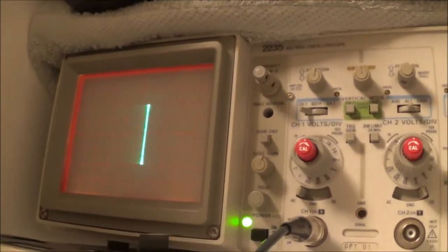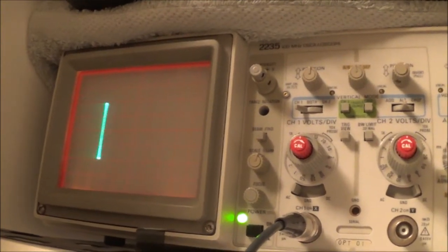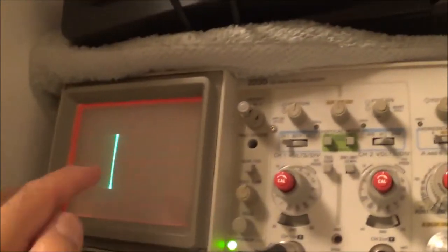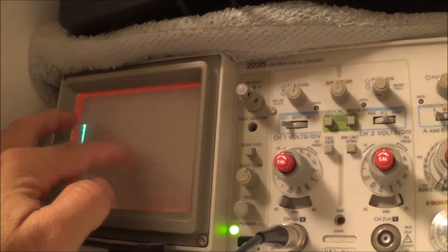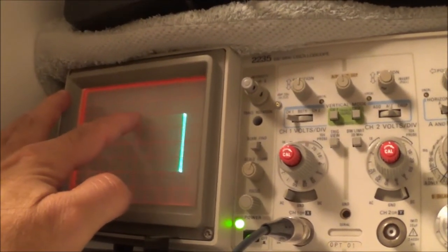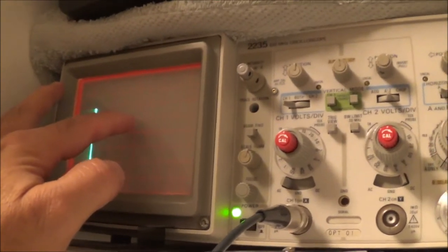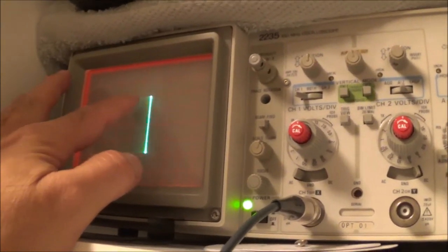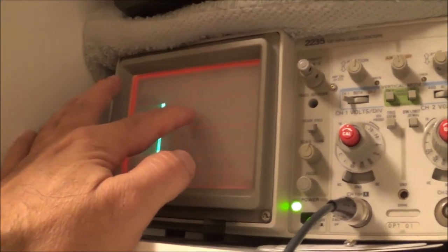I can say this audio generator performs as it should. So I didn't have to, like I said, I could have plotted this. What I would do then is use the reference that I had earlier, which would be exactly 40 graticules. And if it dropped, say, by one graticule, then I would go ahead and take the voltage ratio and then use a table, and that would give me the decibel difference. But in this case, I think I'm okay.